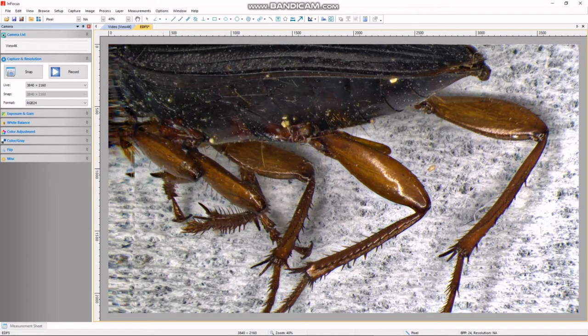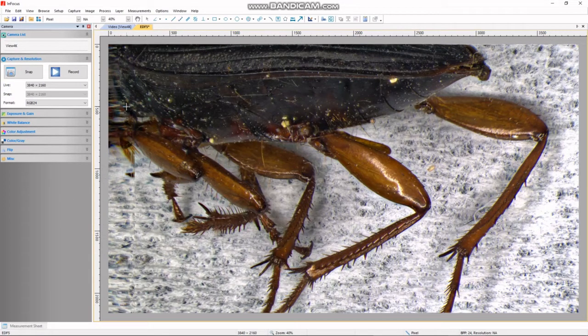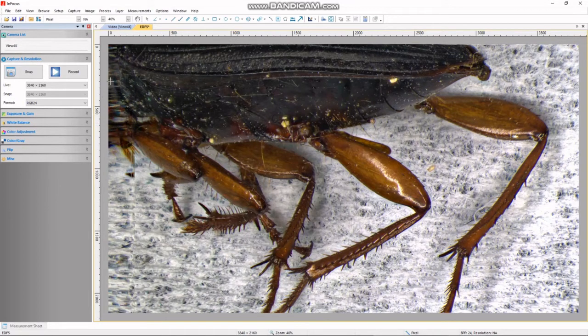One thing to understand is that on stereo microscopes there are actually two optical paths — they're offset and coming in at a slight angle. When we look through with both eyes we achieve that depth perception. However, a camera only has one eye and can only look down one optical path. This is why on the left-hand side of the image you can see some distortion — about an inch of poor image quality — because the sample shifts relative to the camera as you focus up or down. This is called parallax shifting. There are microscopes that can combat that, but for most microscopes you will get this distortion.